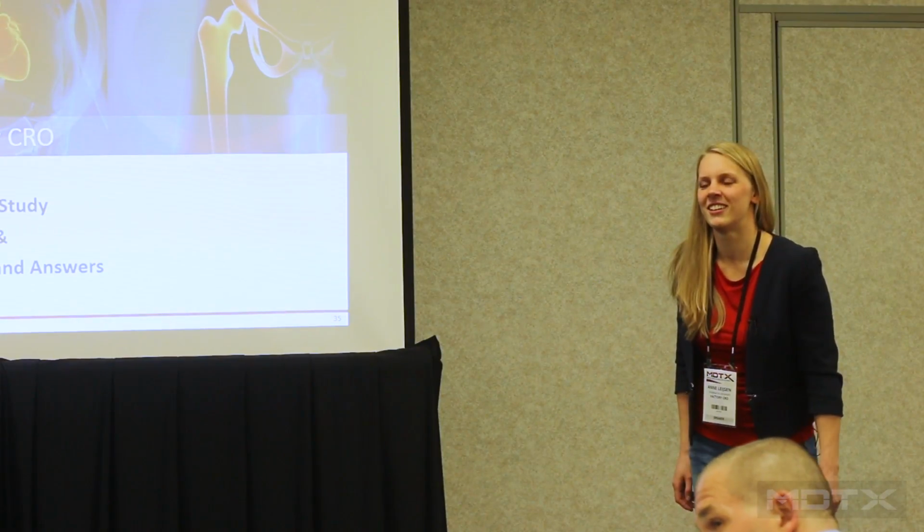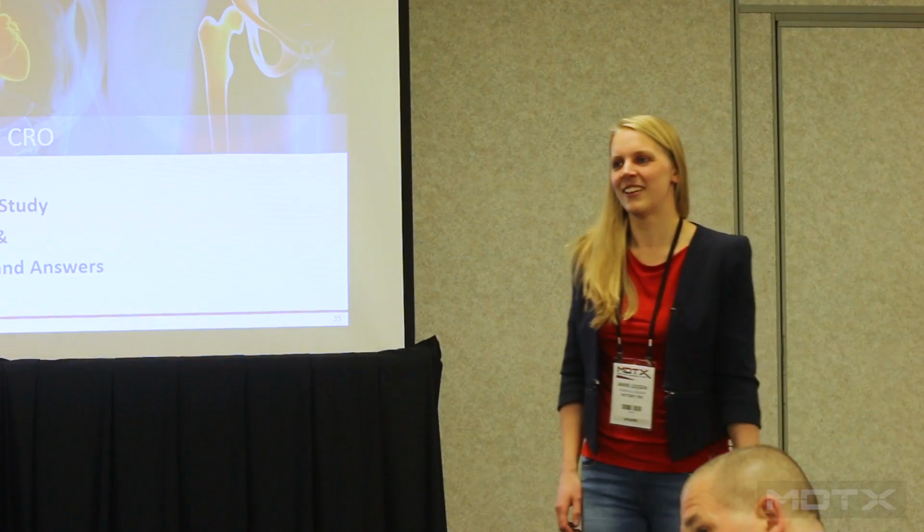You had a question? Yes, along a similar line, for low-risk devices: right now for our CE mark device, we have a justification not to have a PMCF, but could we have one strategy for all three, the post-market surveillance plan, the PMCF, and the PSUR that's coming? I'll look at Christine, she is better placed to answer this question. I mean, it depends. I think you have to address all the products, and you have to provide justification for why you're not doing particular plans or elements. And that comes in that post-market surveillance program, where there are different levels at which you can make different justifications.